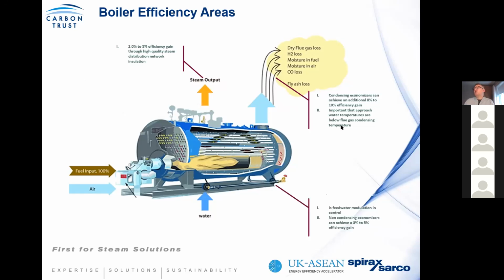When we talked about feed water modulation control, it's important to understand the control that's employed in the boiler. Often we see where processes are very much on and off, then you could find that your feed water system, although designed for modulation, is also very much on and off. And although you may have a non-condensing economizer, you're not getting the full impact of that economizer unless you have a continuous flow of water through it. What you should be looking to do is get about a 3 to 5% efficiency gain from your non-condensing economizer, but this is only determined by the mode of control of the boiler water level.